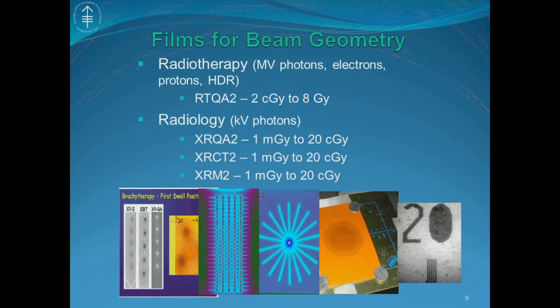There are many different types of film for different purposes. For example, for beam positioning, here are the choices. If you want to do a Linac or HDR QA, you would pick RTQA2 for radiology application. XRQA2 1 or 2 has the highest low energy response. So it is for diagnostic X-ray QA. XRCT2 is for CT, XRM2 is for mammography unit QA. All these types are for the positions or localization of the beam, not for dose QA.